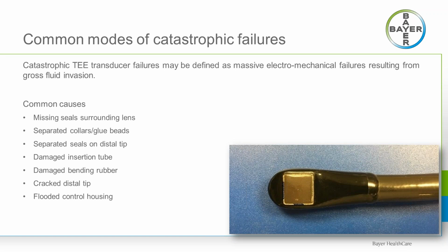So catastrophic failures are extremely common to TEE probes. Catastrophic failures can really be defined as massive electromechanical failures resulting from gross fluid invasion. One of the most common failures on the Philips X72T is a deteriorated seal surrounding the acoustic lens. If not identified and addressed prior to submersion and disinfection, this could result in gross fluid invasion and massive electronic failures. You can see the grayed out areas around the brown square acoustic lens on the distal tip. That's a point of entry for some gross fluid during the cleaning and disinfection cycle.